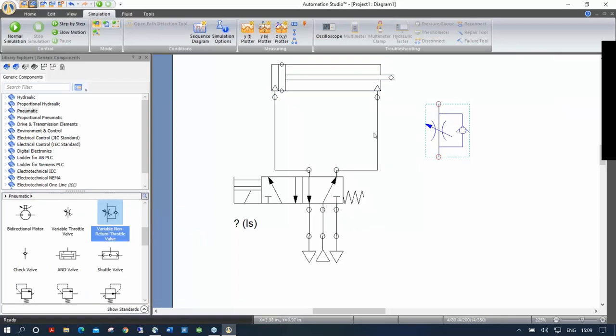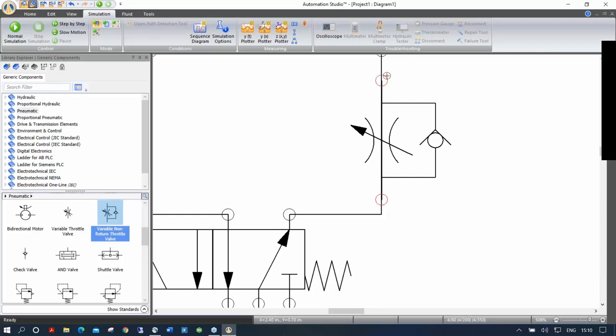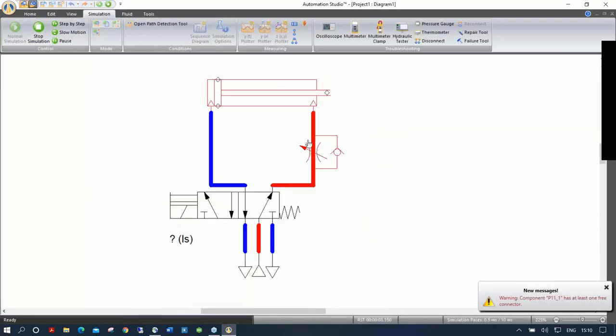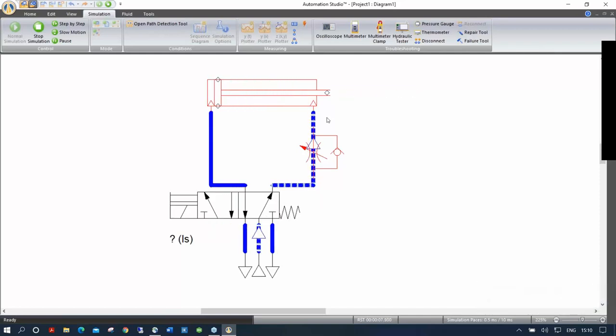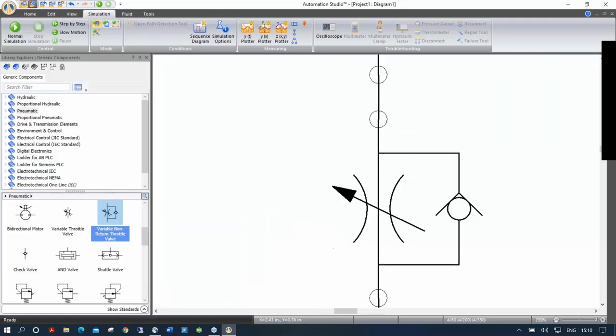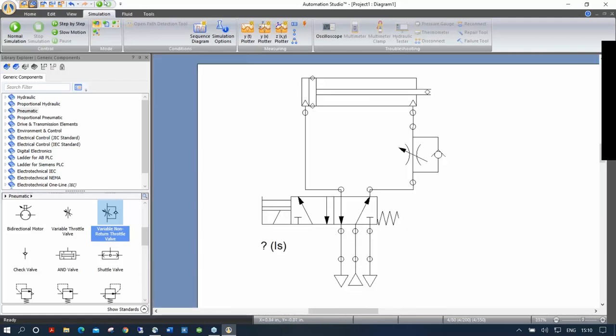I could also bring in a throttle valve and place it on the outlet as a meter-out for the cylinder. There's something important to know: if you place a component on the sheet and bring it onto a line, the red dots mean it's not connected. If you simulate, the line goes through the component — this never happens in Automation Studio. If you see this, it means it's not properly connected. To connect a component already placed on the schematic, hold the Shift key as you bring it onto the line, and it will connect automatically. The circles turn black when connected.